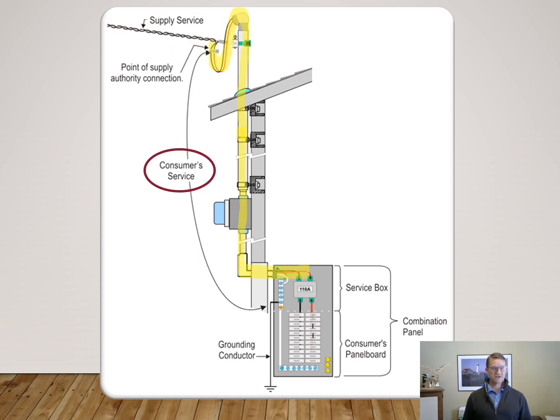After the supply service, we have the consumer service. So from the point of attachment at the supply all the way down through our system to the service box, that is all considered to be the consumer service. And an overhead service, like you see here, it will include the raceway, the service head, the meter base, as well as the service box. The service box is defined as the first point that has both a disconnect as well as an overcurrent device.